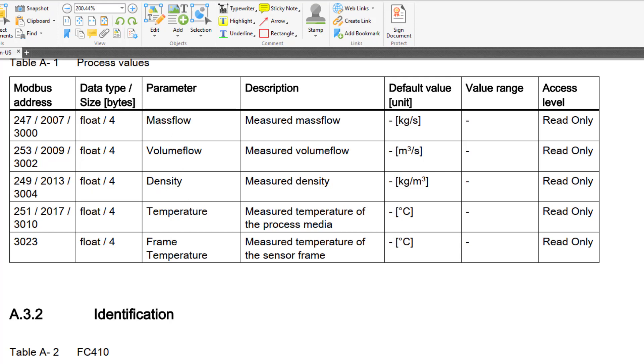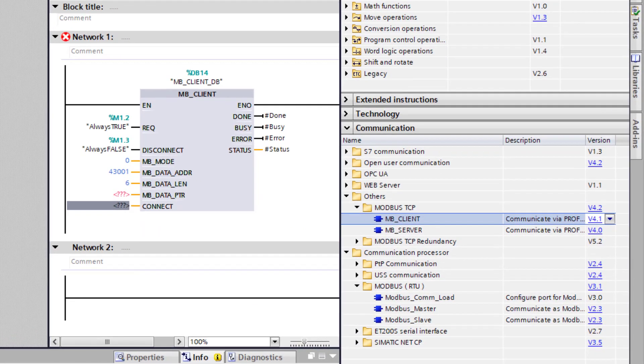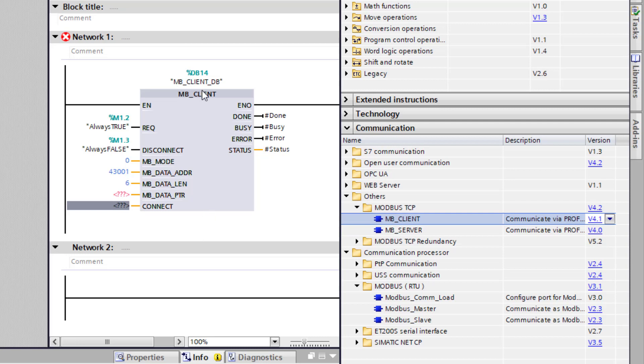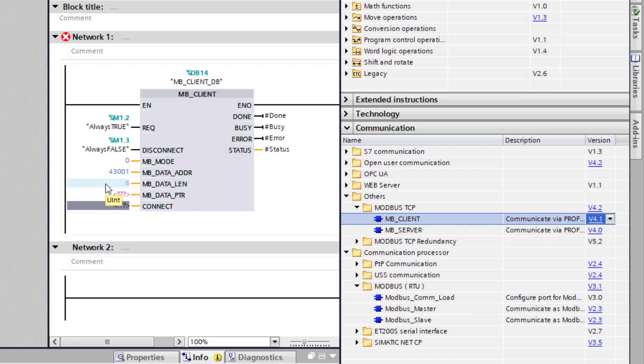So we are going to focus on these 3 process values: mass flow, volume, density, start address 3001. Everything for this device is in the holding register so that is 43001. The length then is 6 because we have 3 double words. What we need to do is add the MB client read to our project. And I have put this into an FC. We have to put it in an FC because we have to use an external data block anyway. So the MB client is situated under the communication tab. If you go to others you have got MB client and depending on what CPU you have got you can change your revision there to 4 or 4.1.